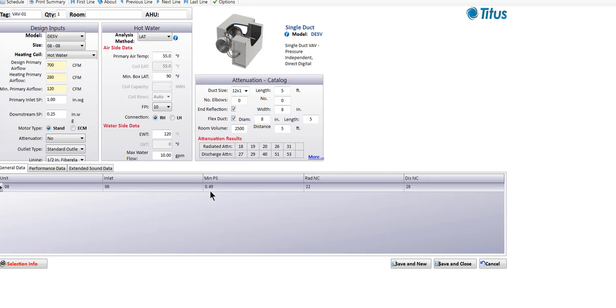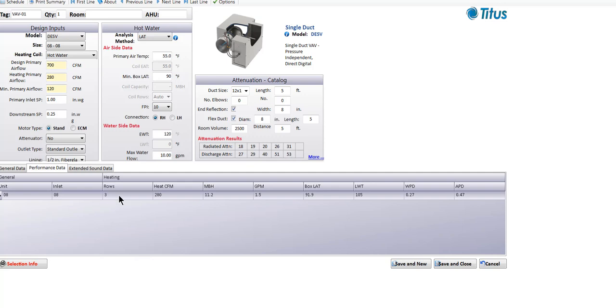Our radiated sound went down even further from NC24 to NC22, and our discharge sound went down from NC31 to NC28. But we've got a three-row coil, which is generally bad news for most people. Most engineers don't like to see more than a two-row coil on a job because they don't like to be penalized by that high air pressure drop through the coil, which costs you all year round. So that's usually to be avoided.